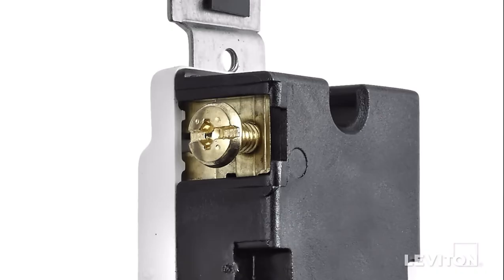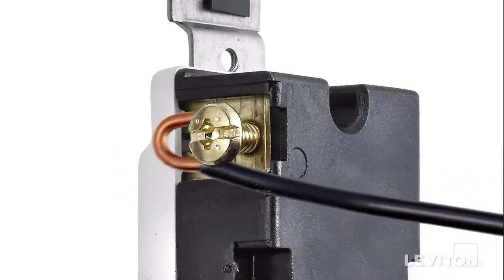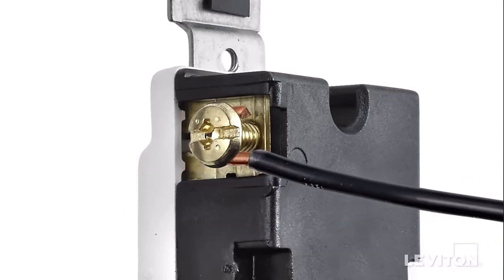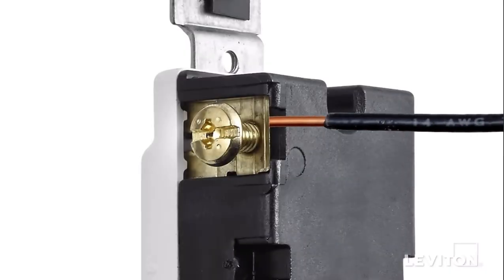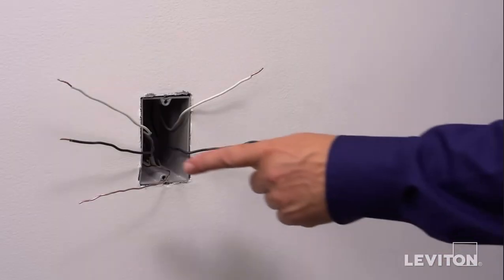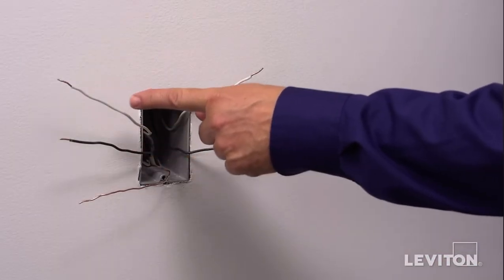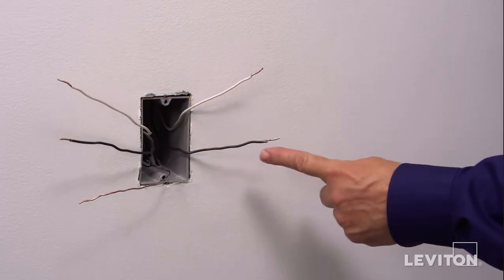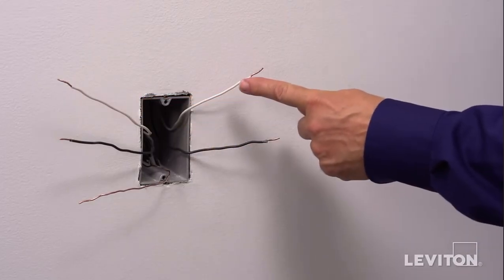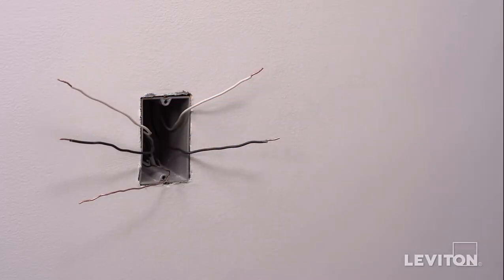These devices offer the option of either wrapping leads around the terminal screws or using an external backwire clamp. We're going to demonstrate backwiring. Begin by identifying wall box wires. It is important not to install one of these devices in an electrical box exceeding 4 wires plus the ground. If you see more than 4 wires plus the ground in the wall box you're working on, contact an electrician.